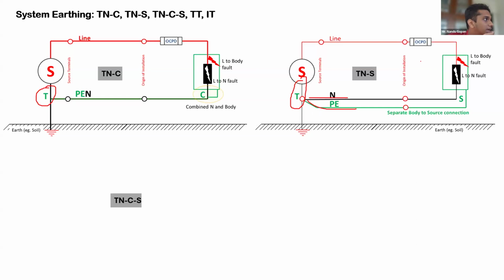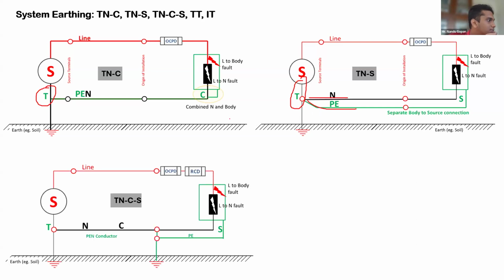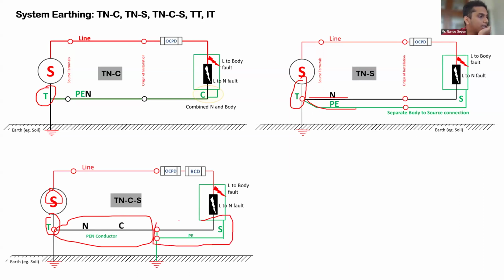Next is TNCS. TNCS is where, from the source, the system referencing will be done here. The neutral and PE will be connected, the neutral and the earth will be connected here. And from here to here, it will be TNC, where the neutral and PE will be connected, having a single PEN conductor. And from here, it will start as a TNCS supply.